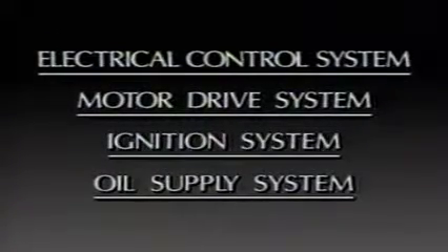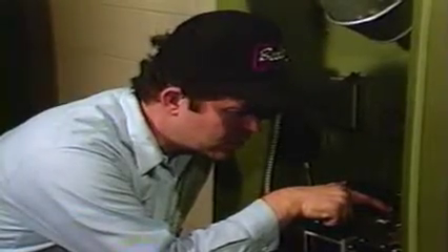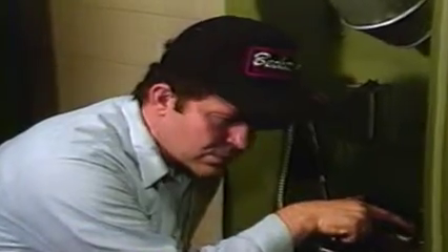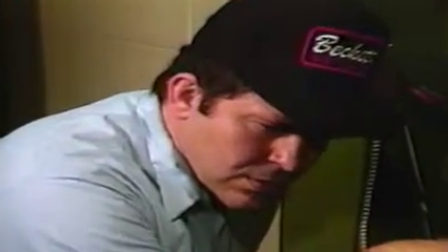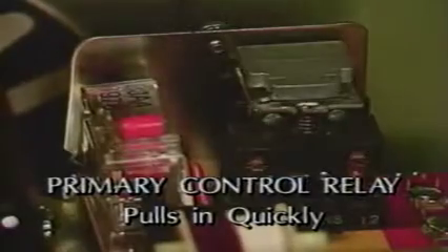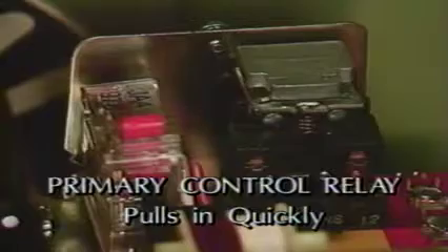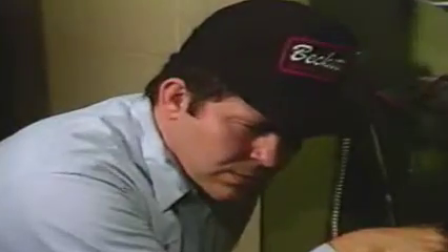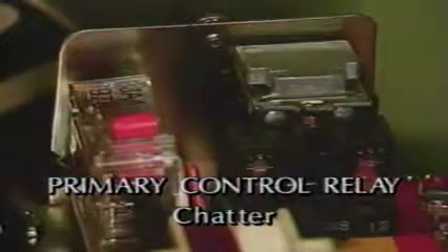After you've done an organized, brief scan of these 4 systems, you should have found the one to pursue in order to find and eliminate the cause of the no heat call. Now, instead of listening to me, listen to the burner for each of these conditions as we go back to the beginning and examine each of the 4 systems in more detail. If there were a problem, you might hear something like this. What if you heard nothing?